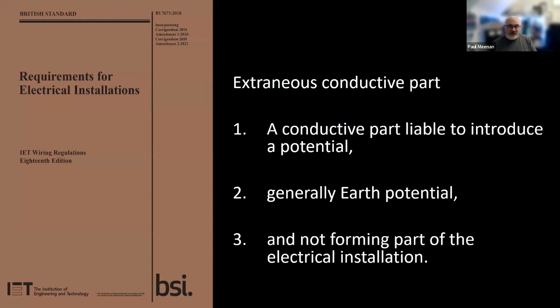But then if we look at extraneous conductive parts, when I was younger I spent a lot of time trying to work out what the difference between the two is. Again, use the rule of three, break it up, highlight it. An extraneous conductive part is a conductive part liable to introduce a potential, a voltage. It's generally at earth potential. So in theory, a pipe that comes out of the ground should be at 0 volts and not form part of the electrical installation. If you have an oil pipe, a gas pipe or a water pipe that comes in from the ground, we assume that it is at 0 volts, so it's extraneous. But what do we do then to ensure safety, so that it doesn't become part of a path?